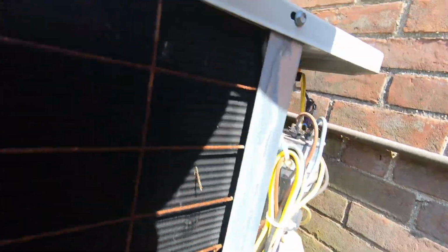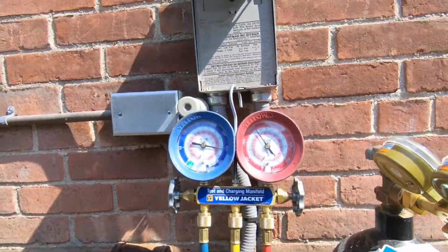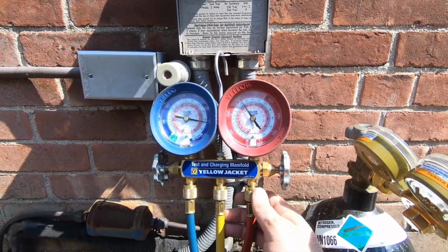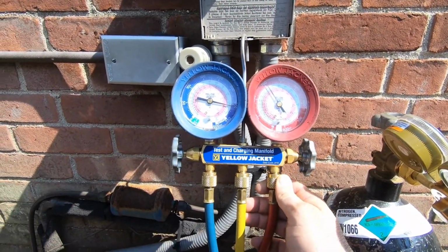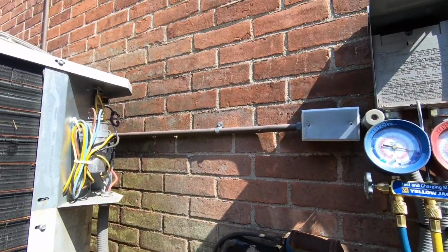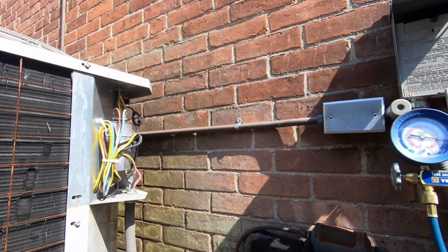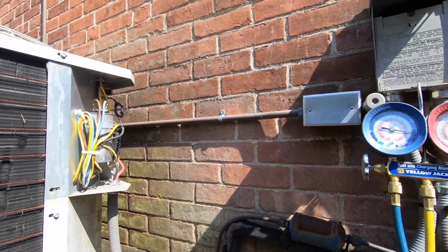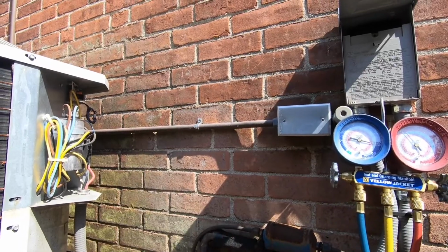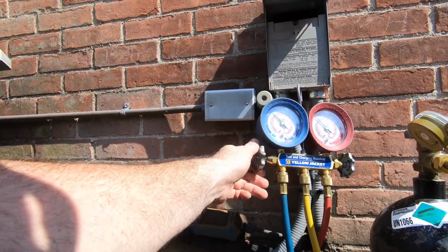Okay, I gotta find out where to get power. Okay. So a half hour has gone by. And we still have the same pressure we had before. Over 305 here, that's a little higher. I don't think they're perfectly calibrated. So, let's get ready for a vacuum.